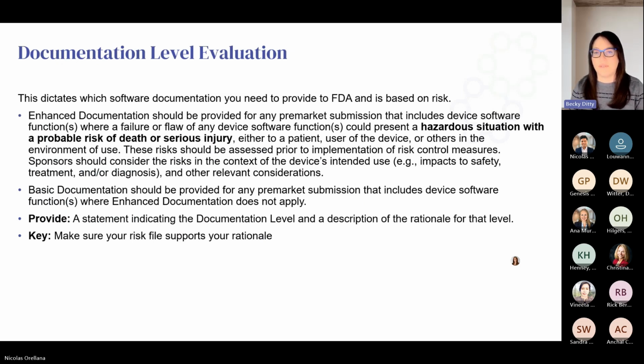One of the first ones is developing your documentation level evaluation. If you're a combination product, then the guidance states that you are most likely going to require enhanced documentation. And those would be products where a hazardous situation with a probable risk of death or serious injury can occur. If your software doesn't fall into that, then you would provide basic documentation. But as I stated before, for combination products, it's going to be enhanced documentation. If you feel that enhanced is not appropriate, that may be something that you discuss with FDA during a pre-sub prior to doing your submission to make sure you understand exactly what's going to be needed.